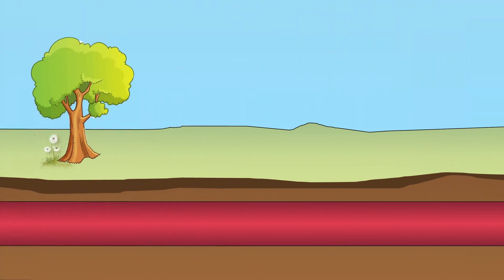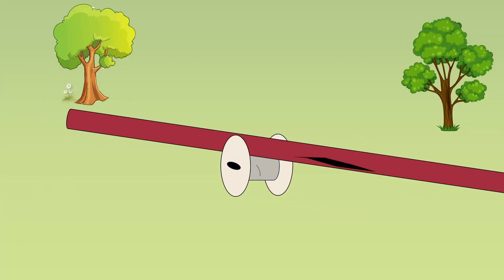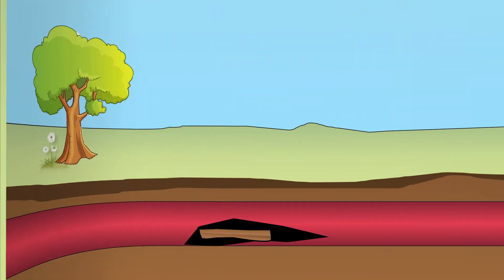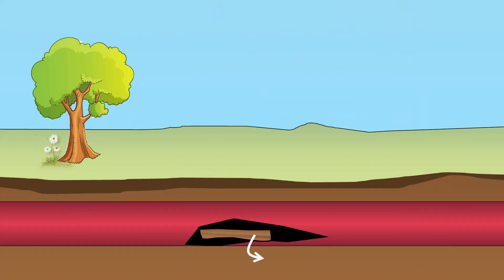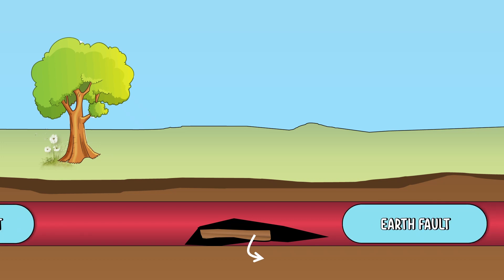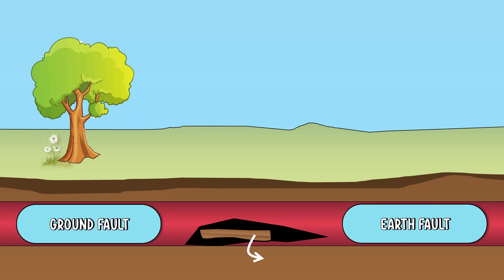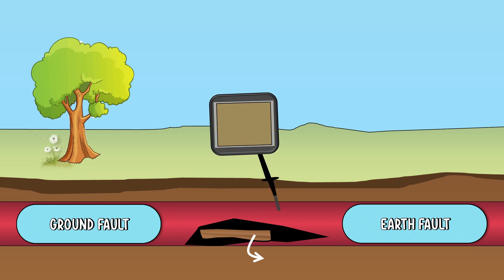Now let's concentrate on earth faults. If the outer layer of the cable is torn during the pulling of the cable or due to any other reason, the conductor of the cable comes in contact with earth — this is called an earth fault or ground fault. To identify this fault, one terminal of the Megger is connected to the conductor and the other terminal is connected to earth. The faulty conductor will give zero resistance.